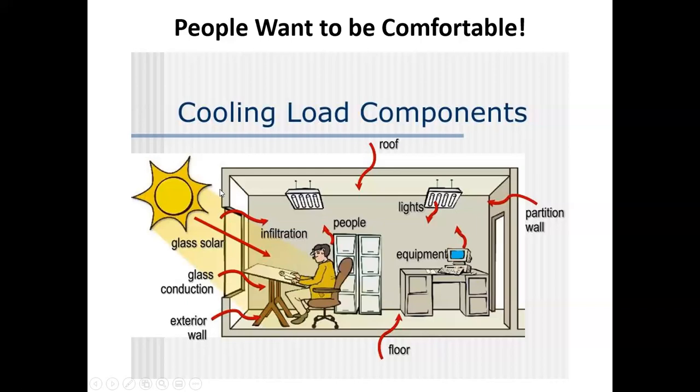Well, that sun hits the side of that building, it's just got a piece of metal and a little bit of insulation. How long does it take that energy to affect the temperature inside that metal building? 10 or 15 minutes? Not long. So that's the other extreme. The massiveness of the construction affects the timing of the energy that comes through the walls and gets released into the space. That's the mass effect on the cooling load.